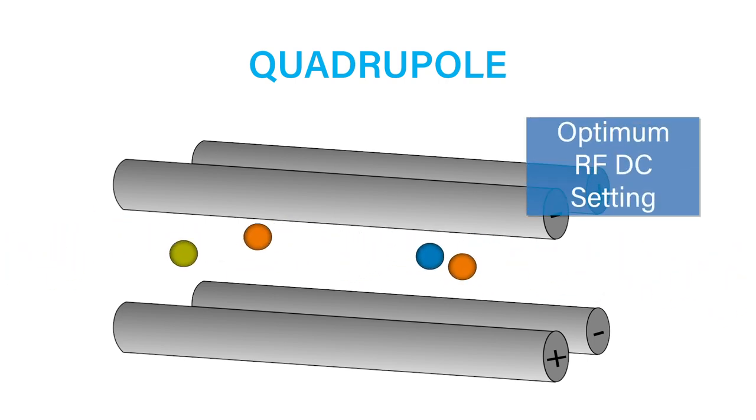Each mass-to-charge ratio has an optimum RF-DC setting, which creates a stable trajectory through the quadrupole. Thus, the quadrupole can be programmed so that only a specific mass-to-charge ratio is stable down the length of the quadrupole.